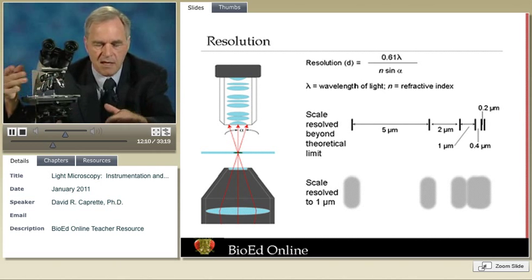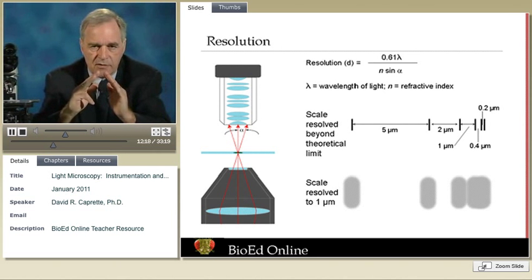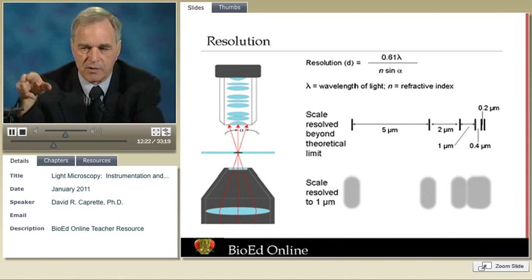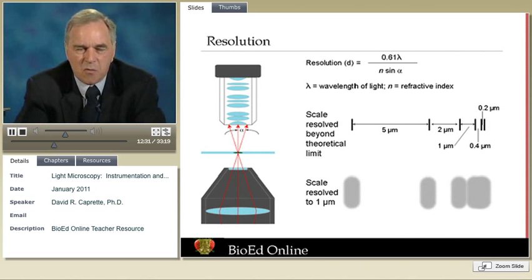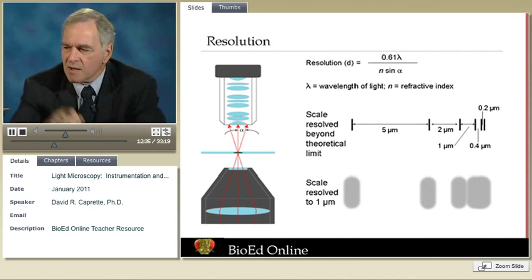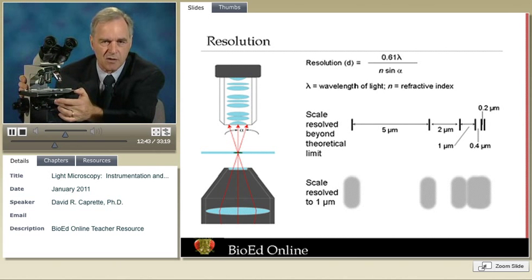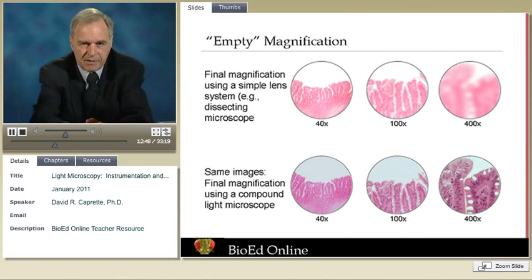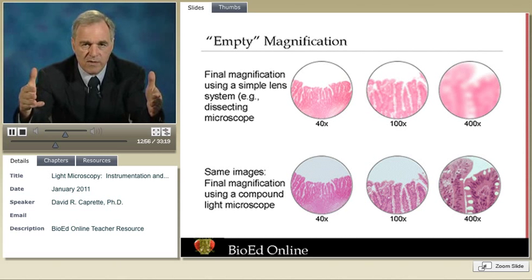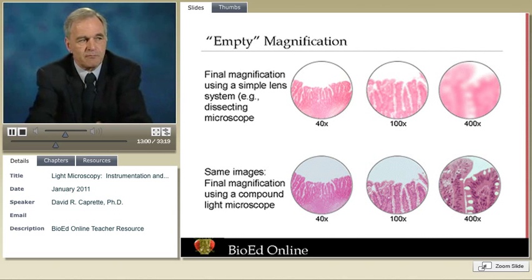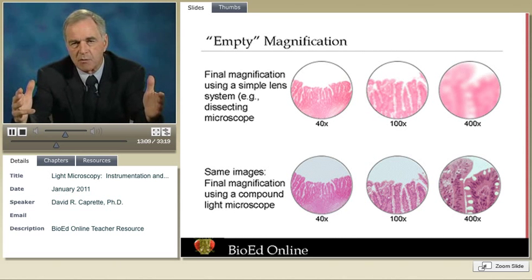The condenser isn't just for making images darker, and it's certainly not just for adjusting illumination. What it does is adjust the angle at which light enters the objective lens so that it matches the numerical aperture of the lens. The condenser must be adjusted for a particular objective lens if you're going to get good resolution. Otherwise, what you get is what we call empty magnification — the same as if you took a magnifying lens and tried to magnify something 100 or 200 times with a single simple lens. In empty magnification, we can make the image larger, but it doesn't improve in resolution — we just get a blur.